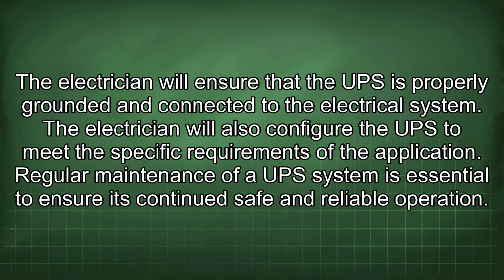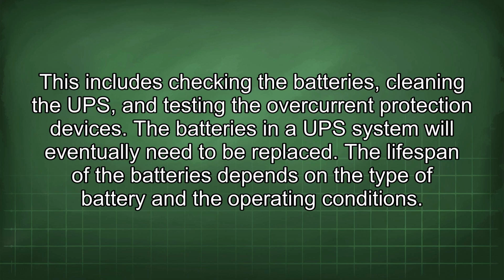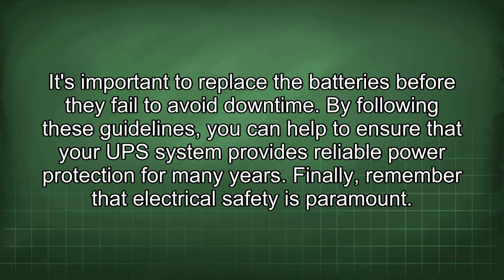Regular maintenance of a UPS system is essential to ensure its continued safe and reliable operation. This includes checking the batteries, cleaning the UPS, and testing the overcurrent protection devices. The batteries in a UPS system will eventually need to be replaced. The lifespan of the batteries depends on the type of battery and the operating conditions. It's important to replace the batteries before they fail to avoid downtime. By following these guidelines, you can help to ensure that your UPS system provides reliable power protection for many years.